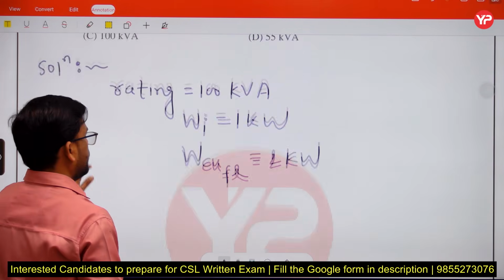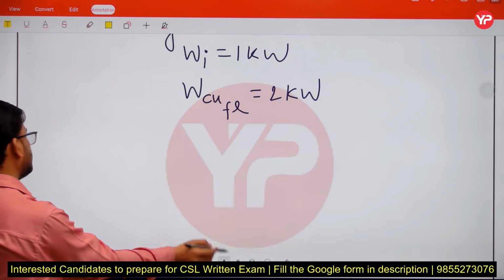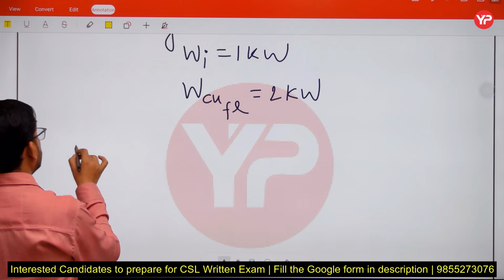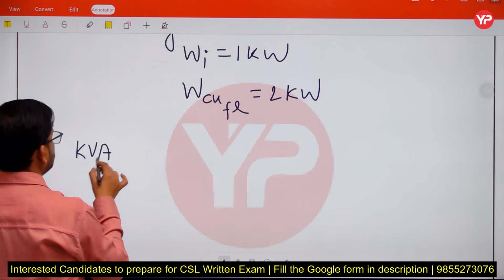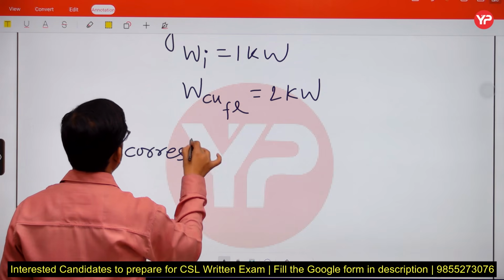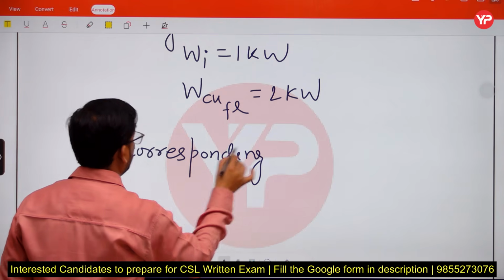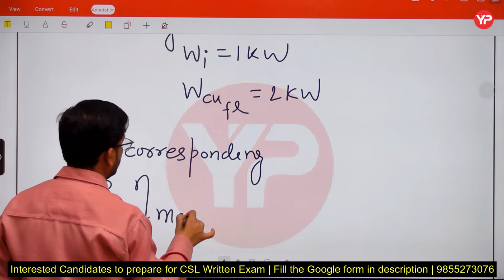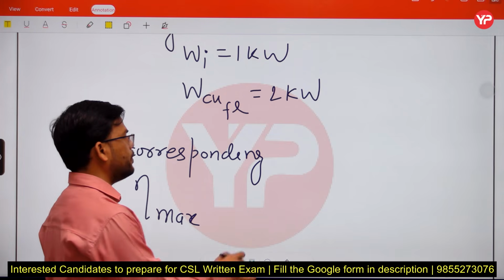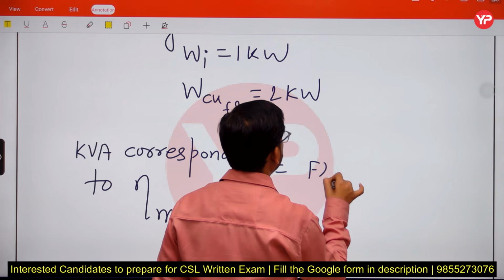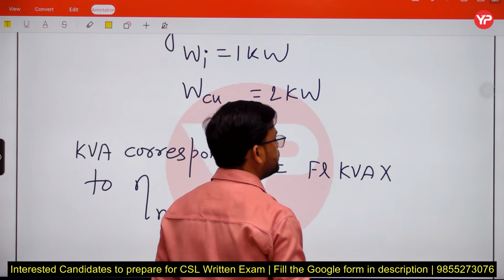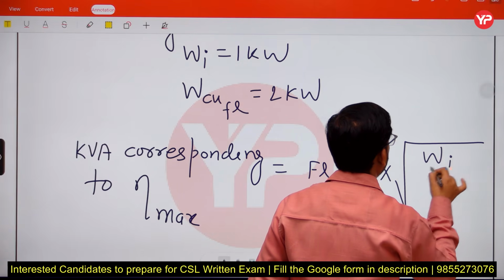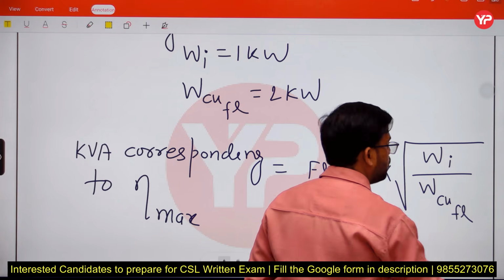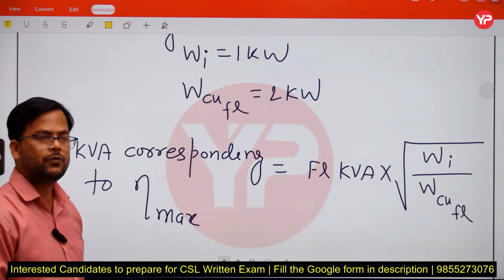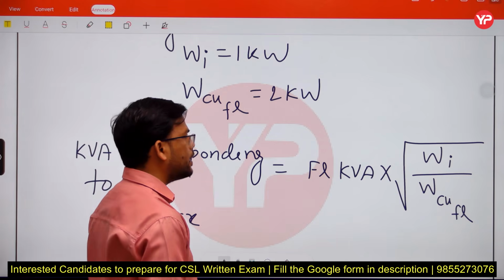Find the load at which the transformer operates at maximum efficiency, that means the kVA corresponding to maximum efficiency. We know load kVA corresponding to maximum efficiency equals full load kVA into under root of iron loss upon full load copper loss.